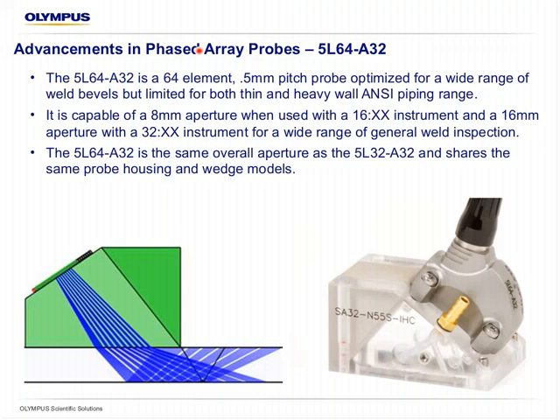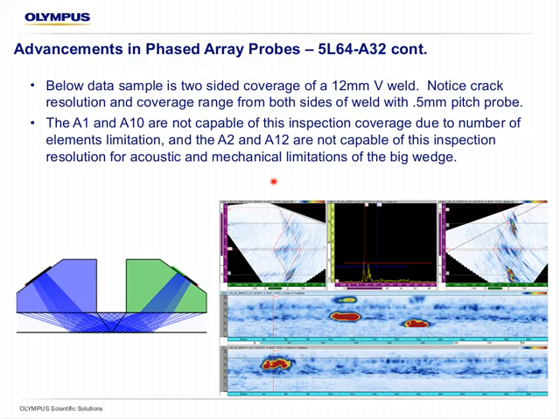The 5L64A32 is a 64 element version, 0.5 millimeter pitch probe in the same housing using the same wedges. Where the A31 covers the thinner side of the ANSI piping chart and is used with the big element pitch 5L32A32 for heavy walls, this probe is a high performance probe designed to be used with a 32 pulser instrument, although it's still compatible with the 16 pulser instrument, for a wide range of the most common size piping in the range of approximately 12 to 25 millimeters.